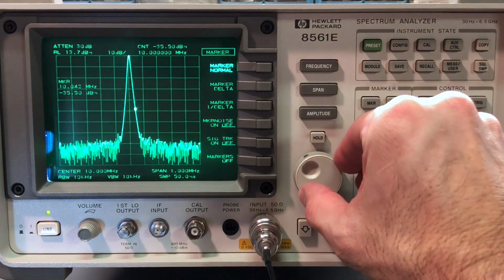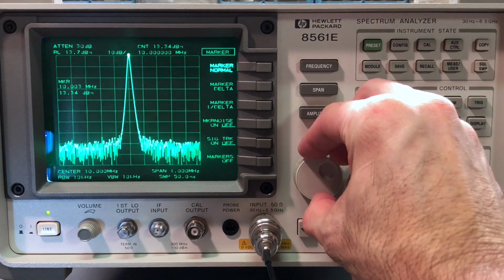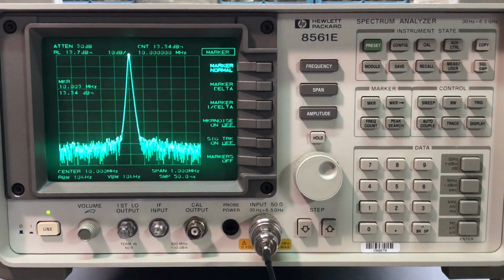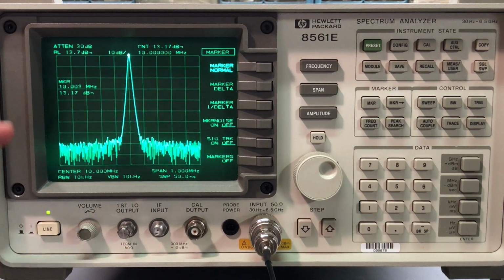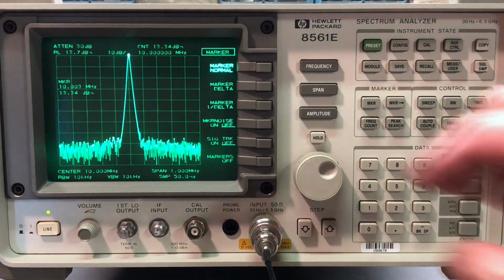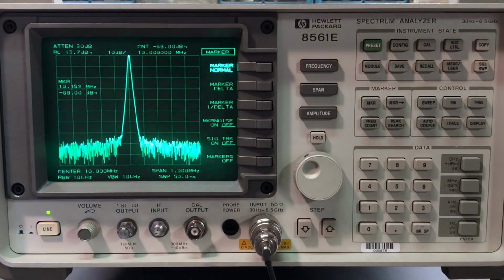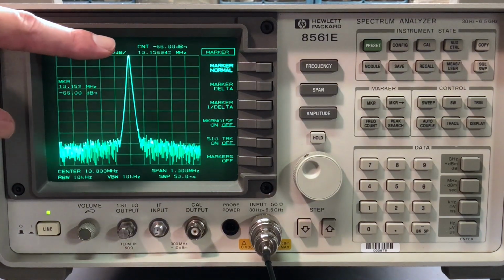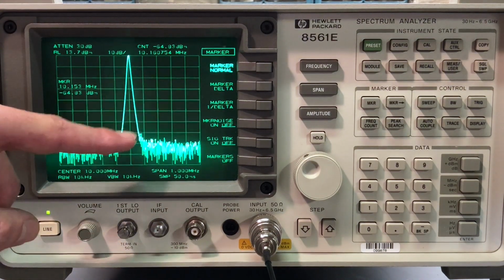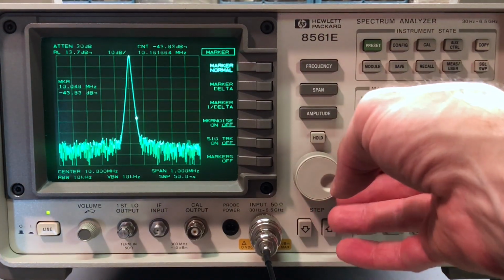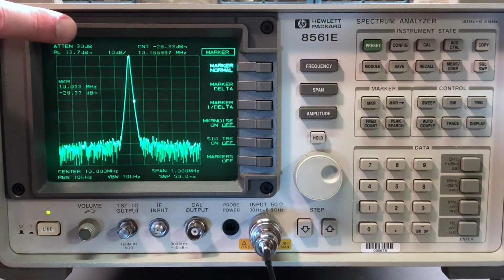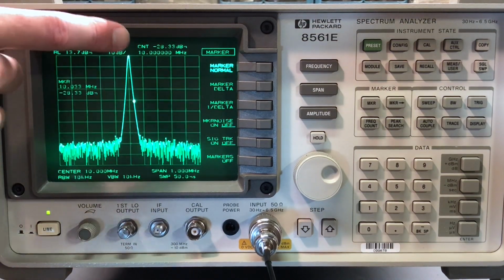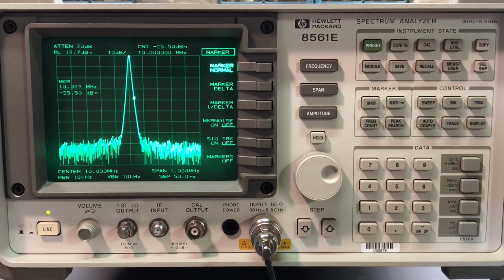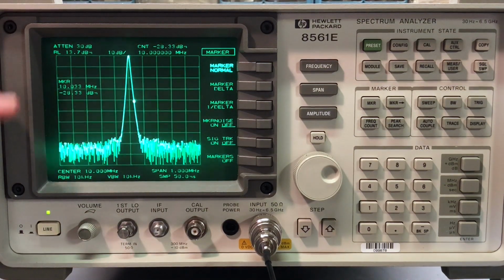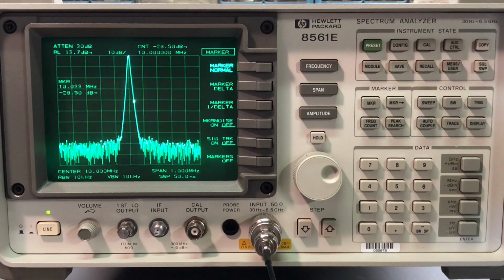If I move the marker up to the peak again, you can see it doesn't change the frequency counter reading. Now, you can see the display is more of a slow update because of that counter function being turned on. But if you move the marker down here into the noise, you can see the counter will then change. See how the frequency has now gone a little bit higher because I've gone higher in frequency. So to have that counter work correctly, you need to have it somewhere on the peak of the signal. It does not need to be at the top. So again, putting the marker on the side right there does give us that 10 megahertz. So the instrument is reading as expected. I've done some checking with it already, and I know that the amplitude is also accurate on here. So it's looking very good, no issues with any of that.